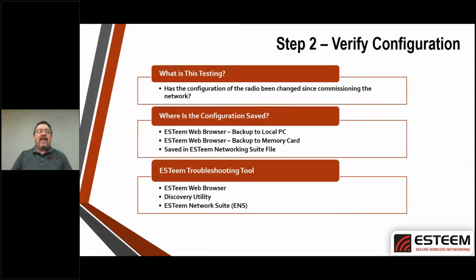So the next thing is, how do we verify the configuration? Things happen. People go out troubleshooting these larger networks, and configurations can get changed, inadvertently loaded into the wrong radio, or backed up. Someone may go out there trying to troubleshoot the network who doesn't really know what they're doing. But what we've got is the ability to validate the communication - in other words, has the radio programming been changed from when the system was commissioned and working?